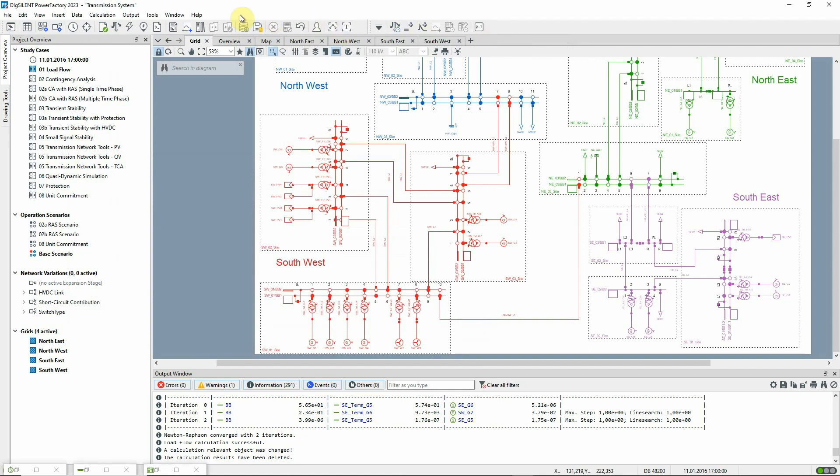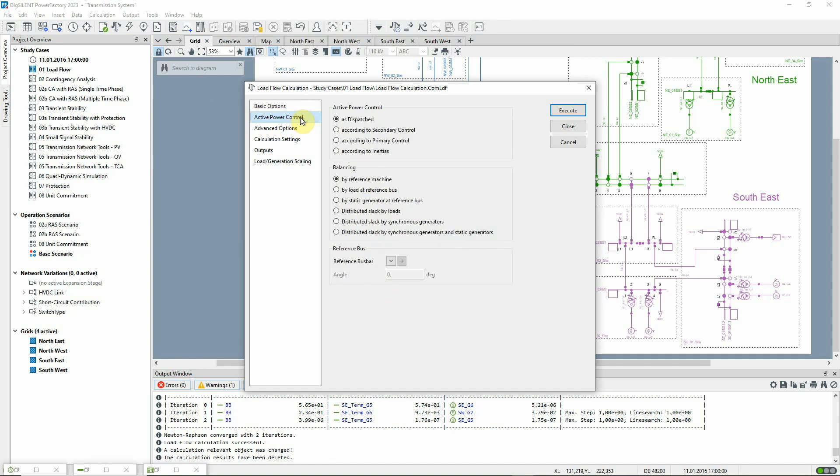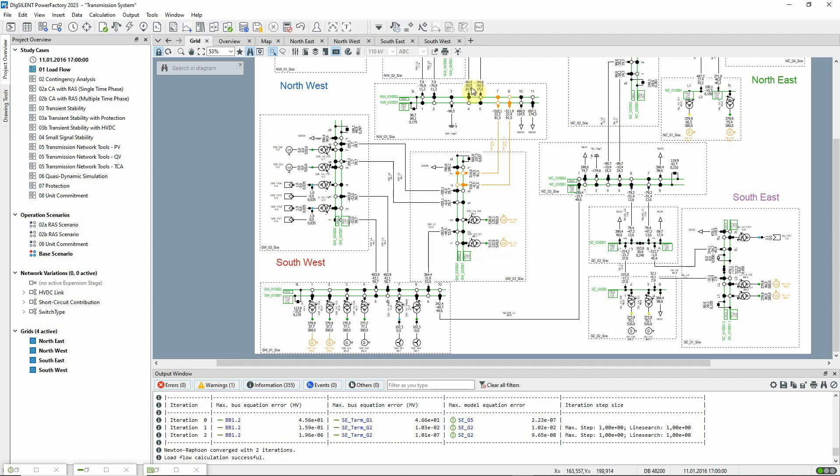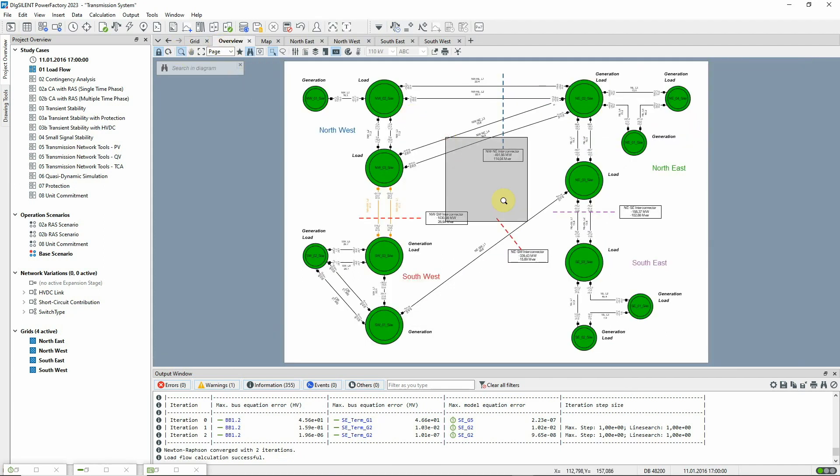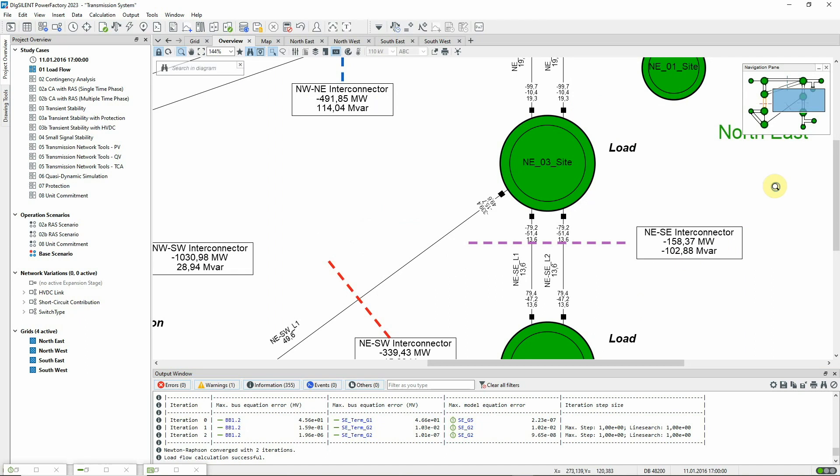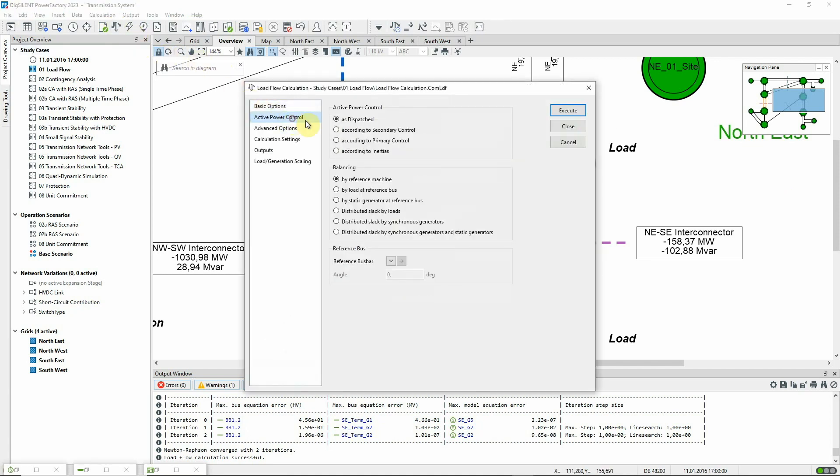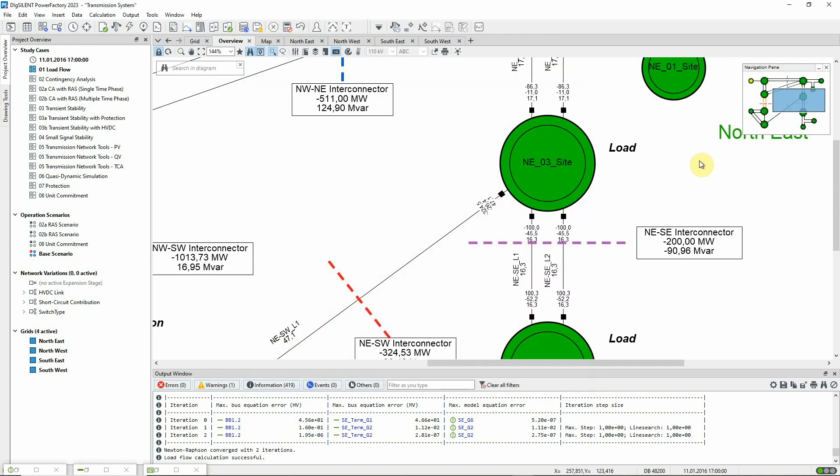To see the impact of changing the active power control mode, let's first run a load flow with the active power control still set to as dispatched. We can see that about 158 megawatts is being exported from the southeast. Now we change the setting to be according to secondary control and run the load flow again. The generation has been adjusted to ensure a 200 megawatt transfer across the boundary.